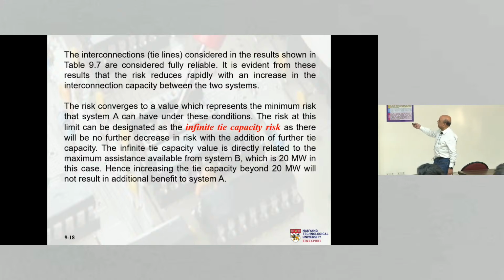So it is evident from these results that the risk reduces whenever we increase the interconnection capacity, up to the limit that system B can support system A. Beyond that, there will not be any benefit. So the risk converges to a value which represents the minimum risk that system A can have under these conditions. The risk is getting better and better, and it will converge to a value that the maximum capacity relates to. The risk at this limit can be designated as the infinite tie capacity risk.